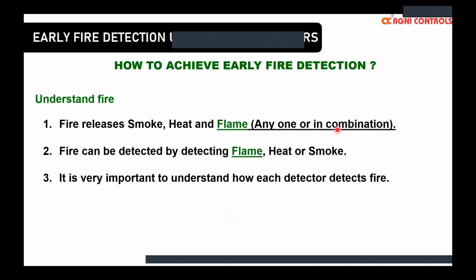So to achieve early fire detection, understand the fire. Fire releases smoke, heat, and flame, in any one or in a combination of various sources. Fire can be detected by using either flame, heat, or smoke. So it is very important for us to understand how each detector can detect fire.